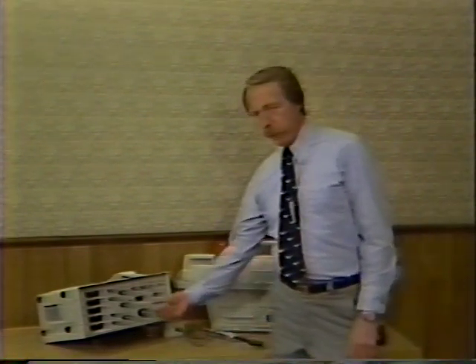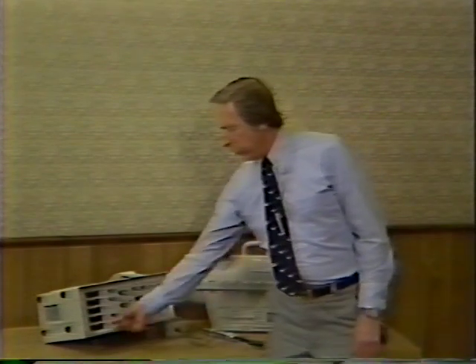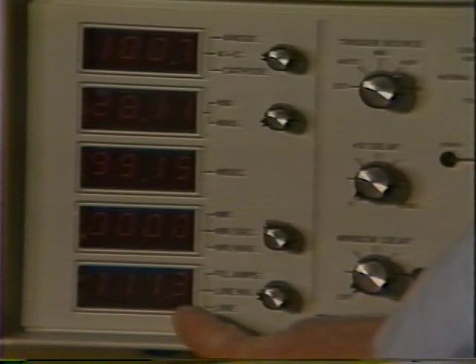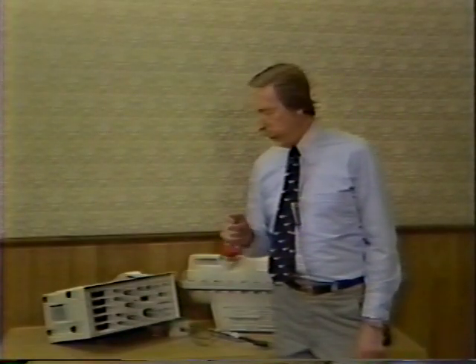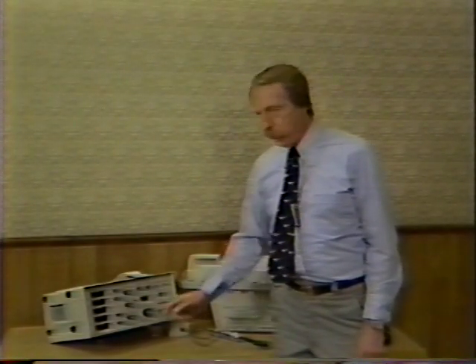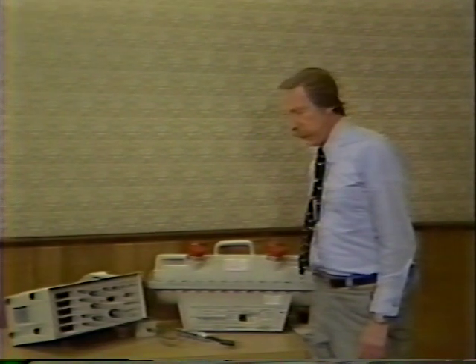Now that we have the Dynalyzer hooked into the circuit, we're ready to use it as we do at Machlett. We turn the power on here. First thing we look at is line no load, or line input voltage. We then switch to filament amperes and read standby filament amperes. We squeeze the trigger on the X-ray generator and read boosted filament amperes. We're now ready for our first shot. We have a simulator with us that will allow us to input the signals to the Dynalyzer very similar to those that we would get from an X-ray generator.